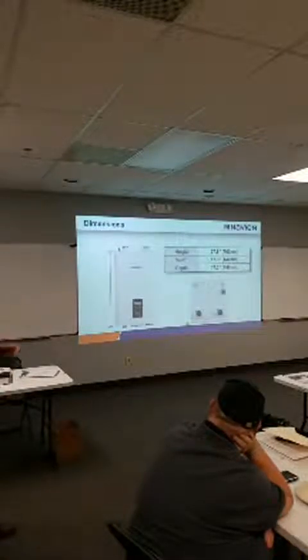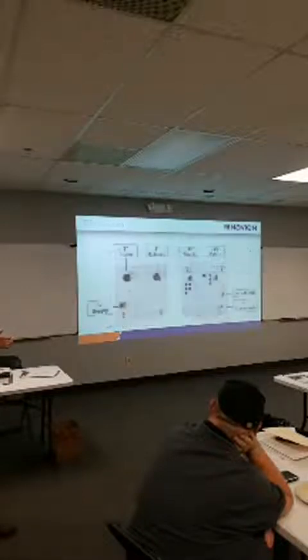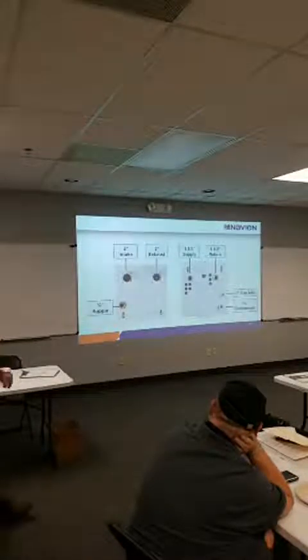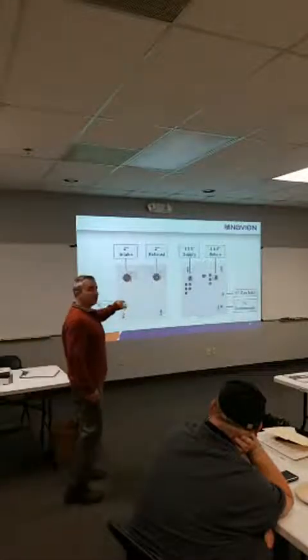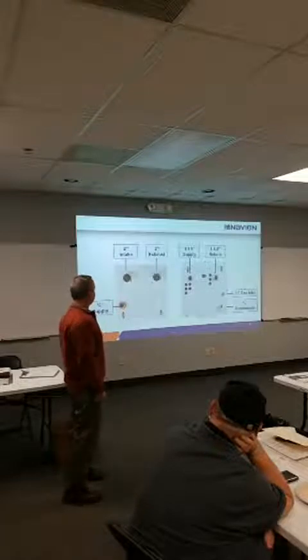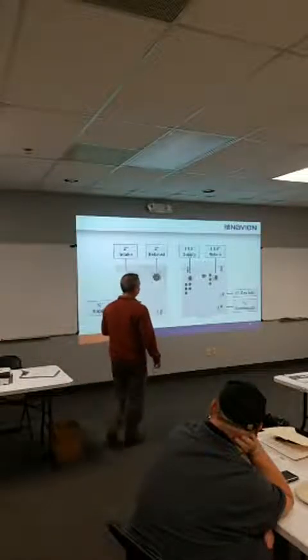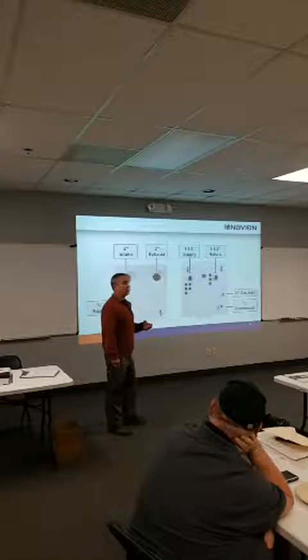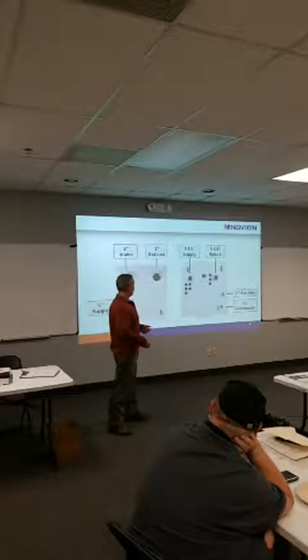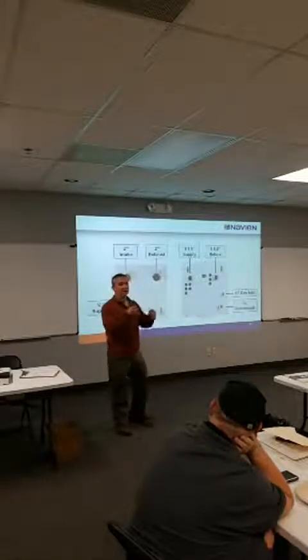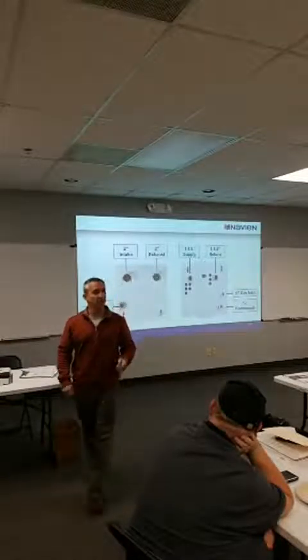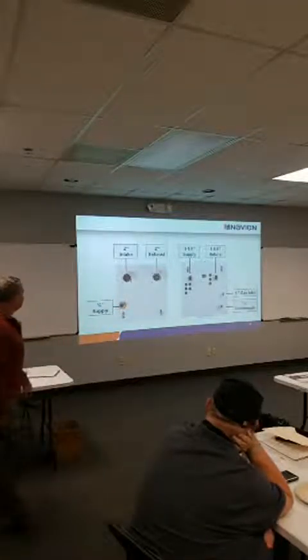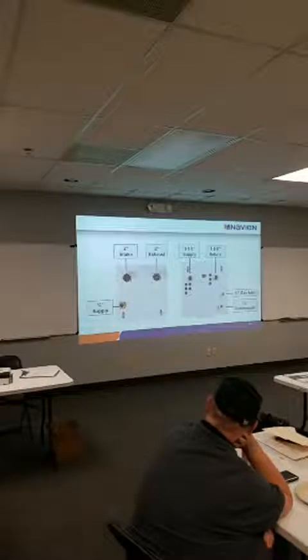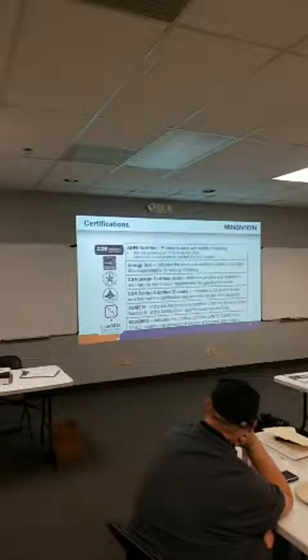So the box is a little bigger, but the top and the bottom basically look the same. You've got 1¼ inch connections instead of 1 inch for your return and supply. It's a 3/4 gas inlet, but we still allow you to do a 1/2 inch gas line up to 24 equivalent feet. The condensate on any of our fire tube product is going to be exposed, but it comes in the box. You basically push it up into that, and it's got that little clip that goes through it. Then you pipe off that exposed condensate. So we check the boxes and all the approvals.